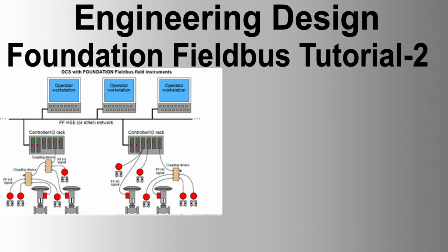Low-pass filter. PV time parameter is the time constant for the low-pass filter in seconds. Alarm generation. LO limit, LO LO limit, HI limit, HI HI limit parameters define alarm thresholds. Permitted modes: OOS, man, and auto. In man mode, you can modify the out value. In auto mode, PV.value and PV.status are copied to out value and out status, respectively.